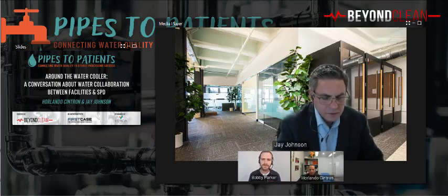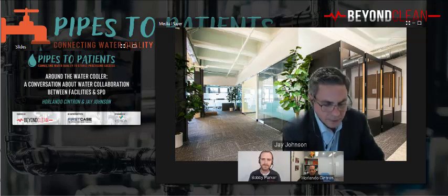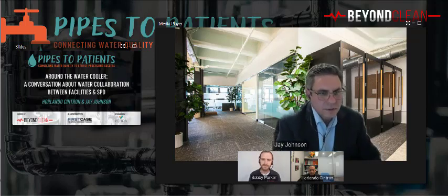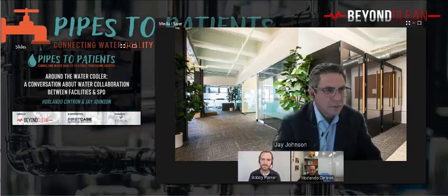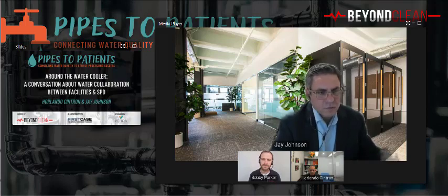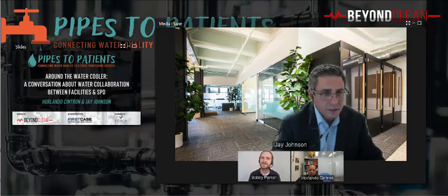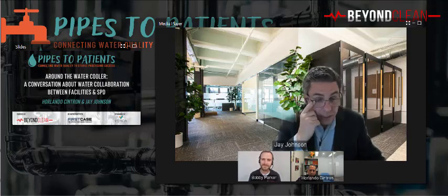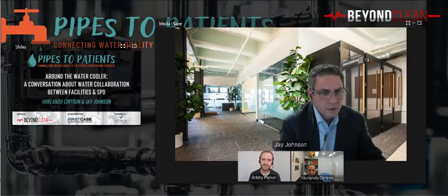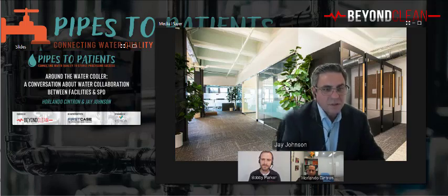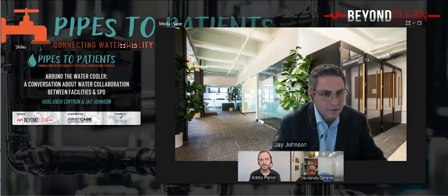You mentioned a water softener, and something like that shutting off or tripping could cause this. But we didn't have softeners everywhere in the facility, so I started asking why that was, and why only in this building, and why only at certain times. What I learned is that the reservoirs feeding New York City, like the Croton Reservoir, draw from different watersheds, and depending on which water source it's coming from, that can change, probably based on rainfall, unexpectedly. Different mineral deposits from the reservoir can greatly change the hardness coming all the way to the city. It's something you never really consider, but it's completely out of your control until you see it. There's nothing you can do proactively until you see the hardness levels rising, then you have to react and solve it through a softener or other means.